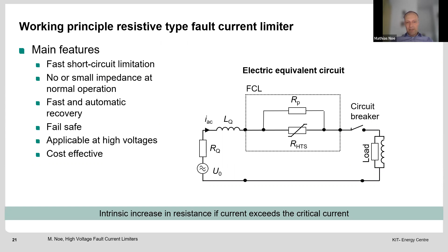This is a typical short circuit limitation. In normal operation, you just see the normal current and nothing else. And within the first rise, the resistance limits the current to a specified fault duration. Then you need some recovery time, but the recovery time can also be 0, and then you start with normal operation again. So there's no conventional device that can have the same features here. That's the nice message for a fault current limiter with superconductors.